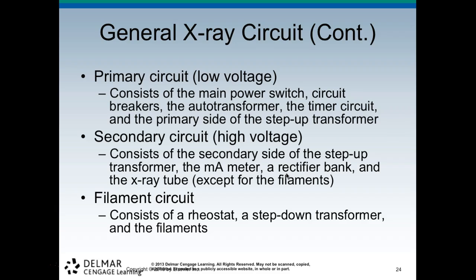All right, so the primary circuit is your low voltage side. It consists of the main power switch, circuit breakers, the autotransformer, the timer circuit, and the primary side of the step-up transformer. The secondary circuit, which is the high voltage side, consists of the secondary side of the step-up transformer, the mA meter, the rectifier bank, and the X-ray tube, except for the filaments. Then there's the filament circuit that consists of the rheostat, the step-down transformer, and the filaments. And I'm going to talk about why it's a step-down transformer on the filament side.